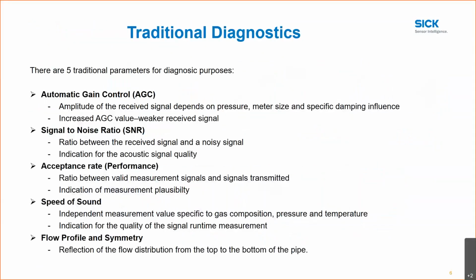So let's start out by talking about some of the traditional diagnostics. I selected five of the major traditional parameters for diagnostic purposes. These include the automatic gain control, signal to noise ratio, acceptance rate, speed of sound, flow profile, and symmetry. These have been around for a long time, since the meter was first developed, and of course they continue to be used because that's a good basis for doing our diagnostics. Let's talk a little bit about automatic gain control. Again, we're not going to spend a lot of time on this, but I wanted to show you some of the existing diagnostics and what's new down the road.